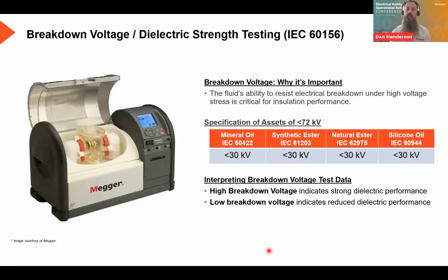Yeah, I mean, this is the important bit, just to make sure that you're doing the right tests against the standard. A company that I'd done some work with had done testing against their own internal standard that they'd passed down over time. And it was purely water content and acidity, and essentially a flash test. And they did that against their own internal standard, not an international standard. When a sample was done a couple of years ago, against the standard for that geographical location, it was identified on a lot of their assets that they had a significant breakdown voltage reduction on most of their transformers. So they were 11 kV assets as an example, but most of those were down to sort of 16, 17 kV. When you think of all the standards saying less than 30 kV.